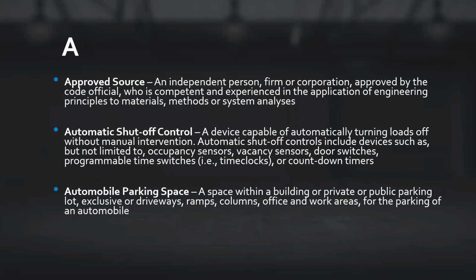It's a device capable of automatically turning off loads without manual intervention. Automatic shutoff controls include devices such as, but not limited to, occupant sensors, vacancy sensors, door switches, and programmable time switches such as time clocks or countdown timers. So if somebody walks in and turns on a timer that counts down 20 minutes, that's the same kind of thing. If it's an occupant sensor, once someone leaves it starts counting down digitally and then turns off, same kind of thing. Door switches work similarly, once a door opens it triggers a timer to start, then shuts off.